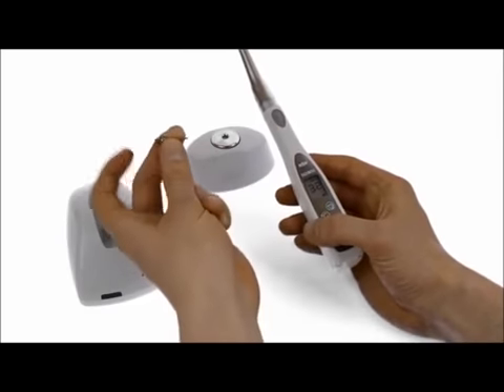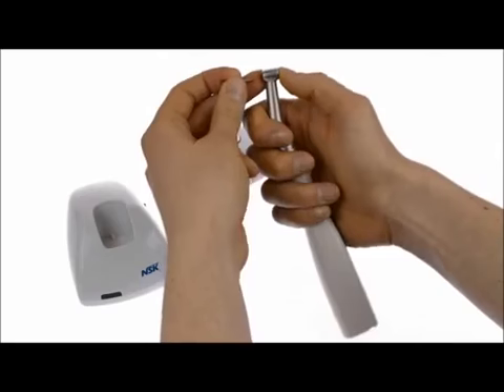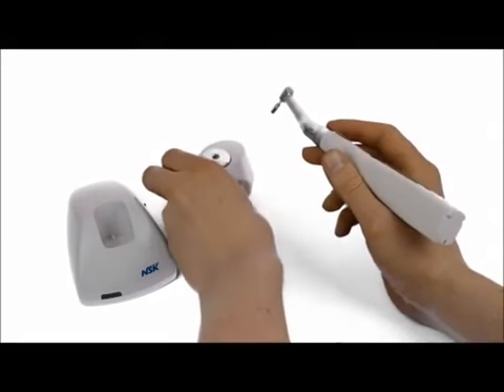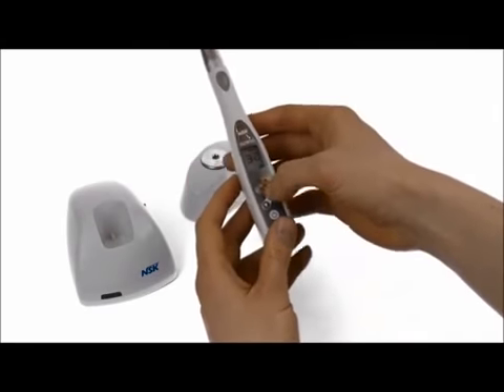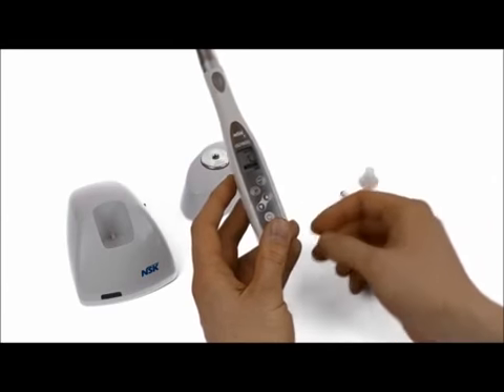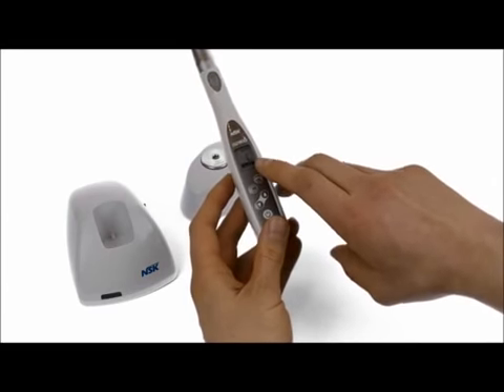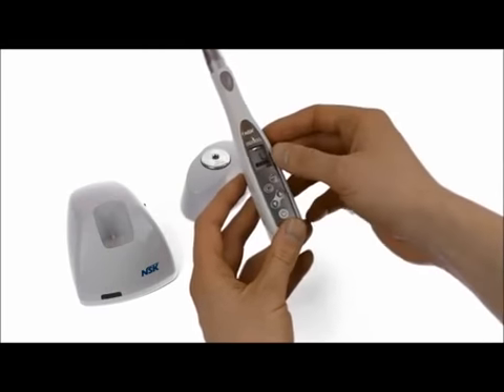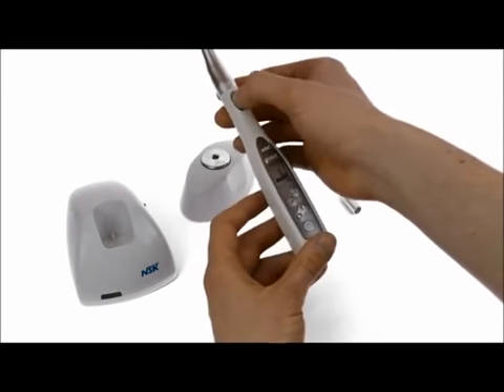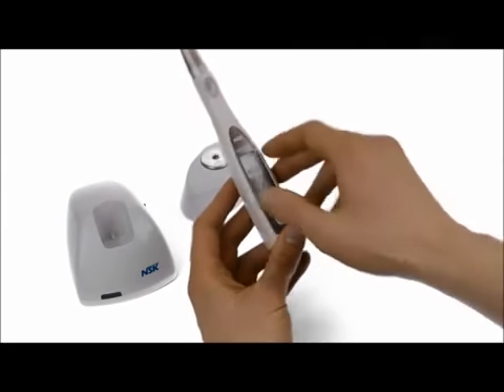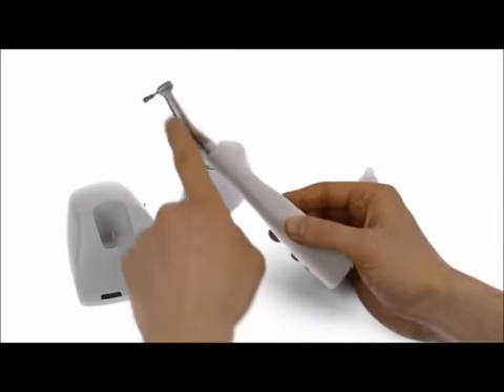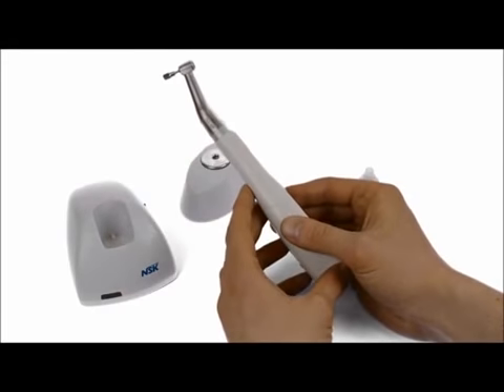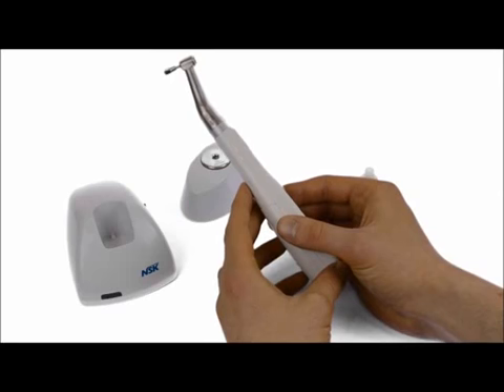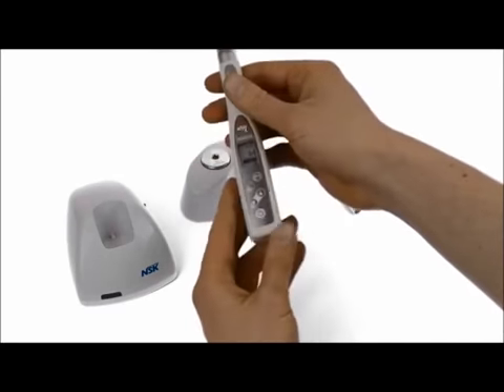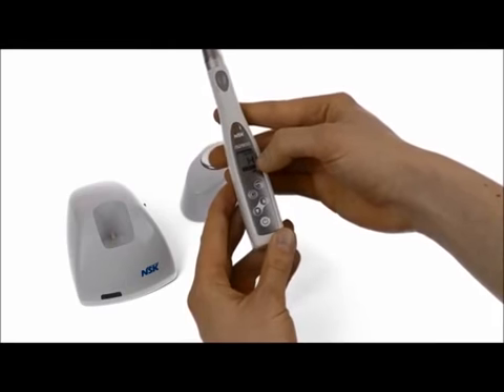So this is the calibration burr, and this clicks into the handpiece like so, and then you take your torque calibration unit and have that ready. Then you press and hold the letter C on the motor, and then it will beep twice, and you'll see the letter L displayed and cal. So to activate the initial phase, you press this button once, and it will count down from 3, and then the handpiece will begin to rotate. After a few seconds, it will then beep again, and then the letter L is replaced by the letter H, and this is for high torque.